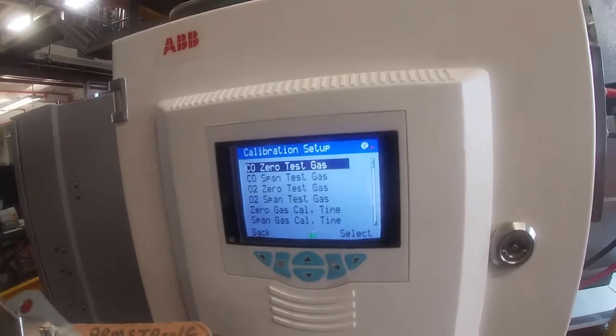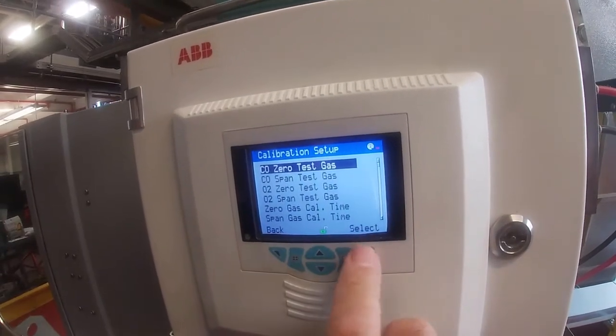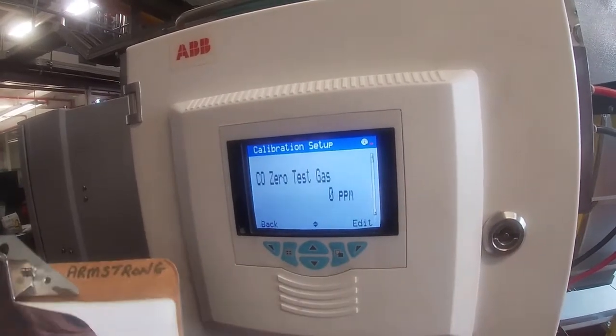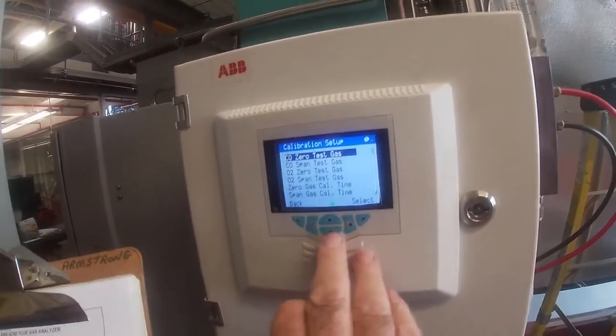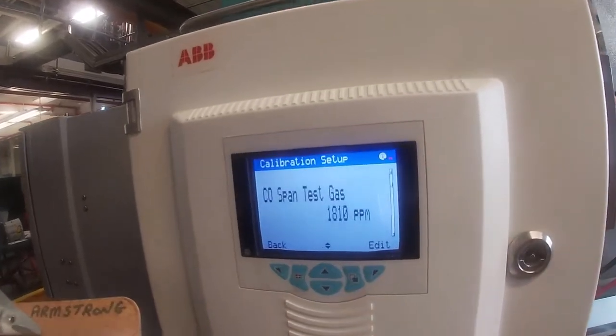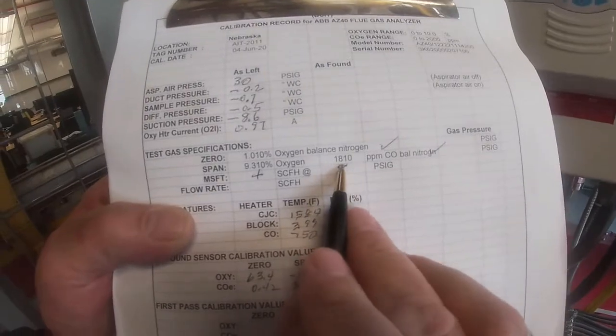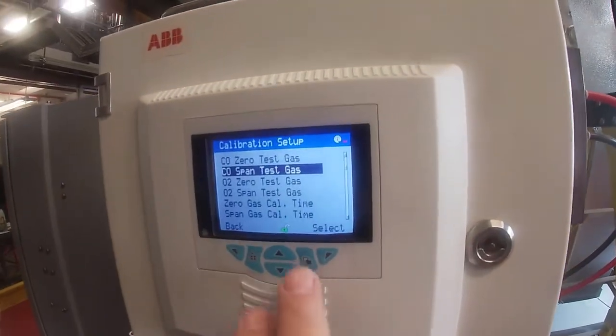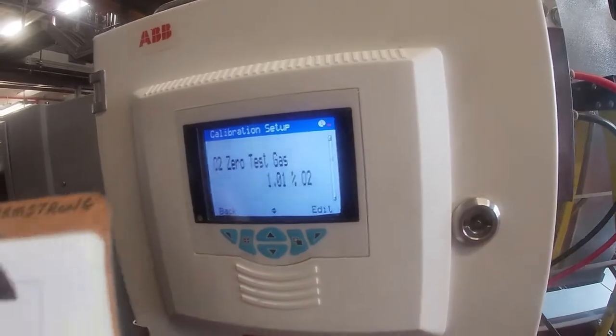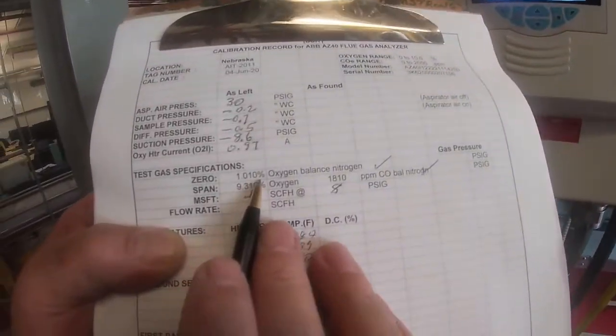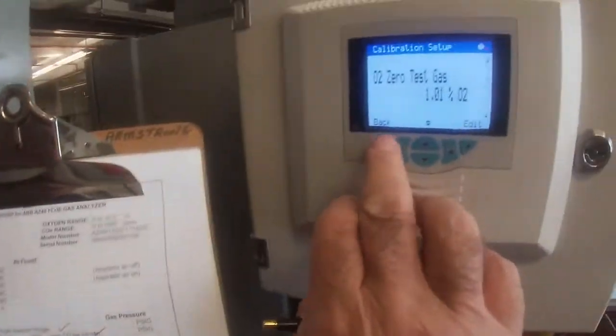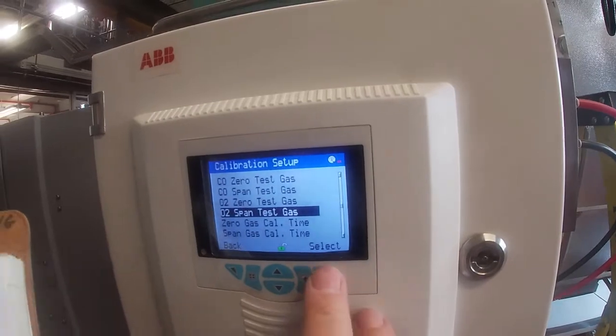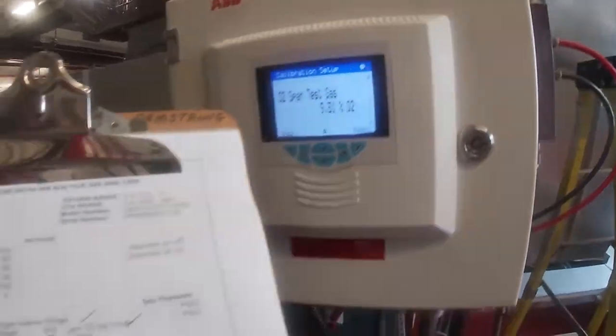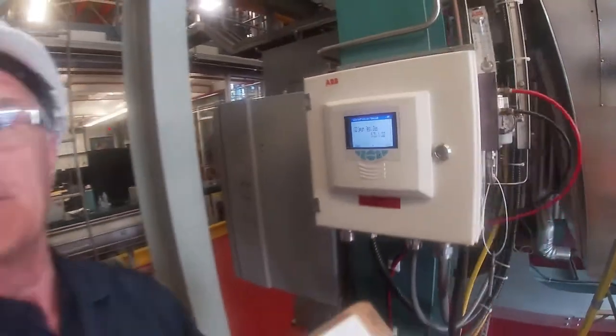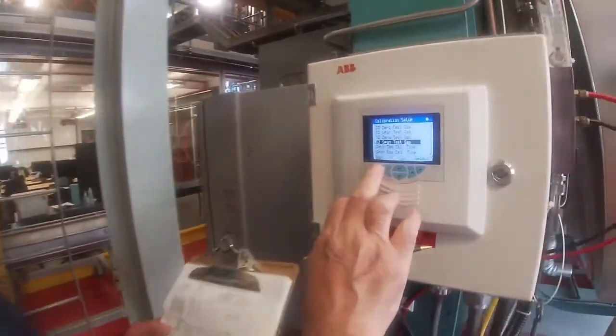Select calibration setup. The zero gas is at 0 ppm, that's right, there was no CO in it. Back, the CO span gas was sitting at 1810, that's what's on my sheet here, that's what's in that bottle. Back, the O2 zero gas is sitting at 1.01, which is what the bottle says it's got in it. And I'll go back, and the O2 span gas says it's 9.31, which is what was on our gas bottle. So the analyzer knows what we've got in these bottles.